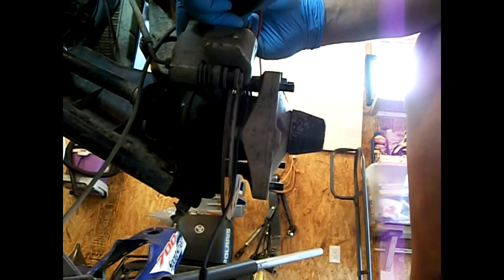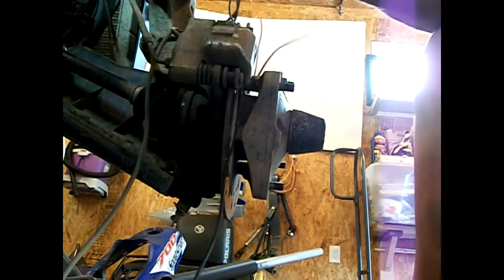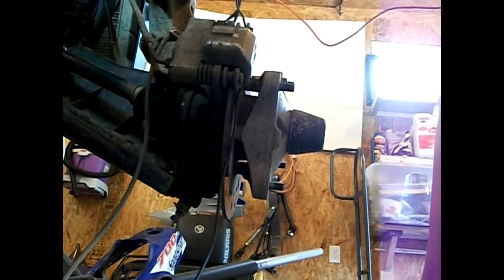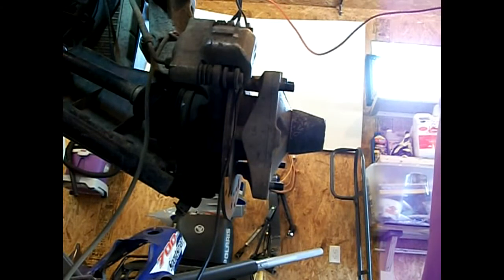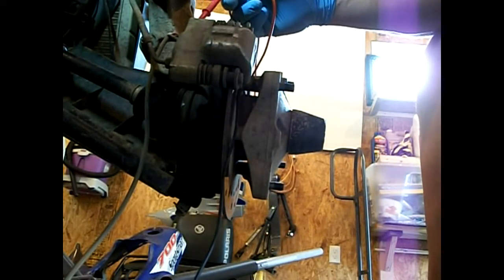Probes in on one end, piercing this end. Good tone, good tone. So the wiring is okay, that rules out the possibility of a break in the line causing the malfunction.